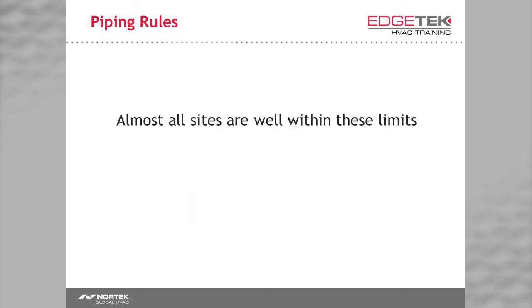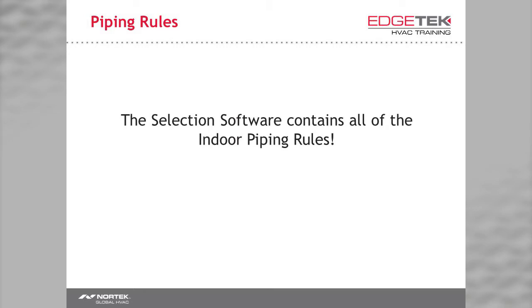As you can imagine, 99.99% of the time, potential VRF sites are well within these limits. In the 0.01% left over, you can probably move some equipment around or reroute the piping. If not, I honestly have no idea what magical piece of equipment you'd use. Although those rules might sound complicated, the easiest way to skirt all of that adding up is to use our VRF selection software. All of the piping rules are pre-programmed in to ensure you won't make a mistake.